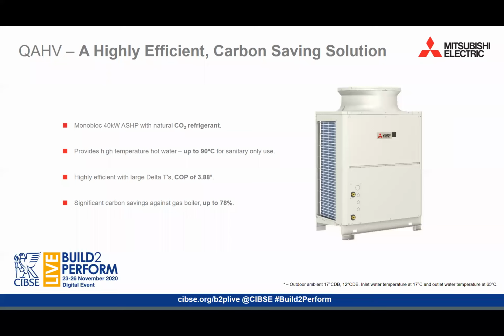The QAHV is a 40 kilowatt air-sourced monoblock heat pump that uses CO2 as a refrigerant. Capable of flow temperatures from 55 to 90 degrees Celsius, the unit is highly efficient and capable of providing large delta Ts. The main value of the QAHV in the growth of the electrification of heat is its ability to show carbon savings against gas-driven technology when flow temperatures are high.